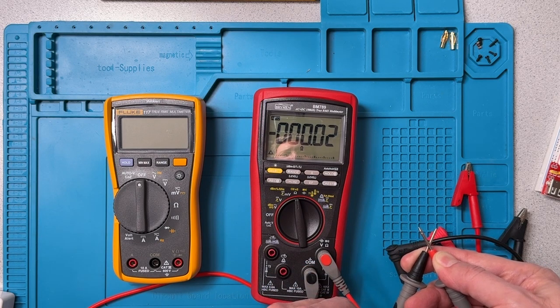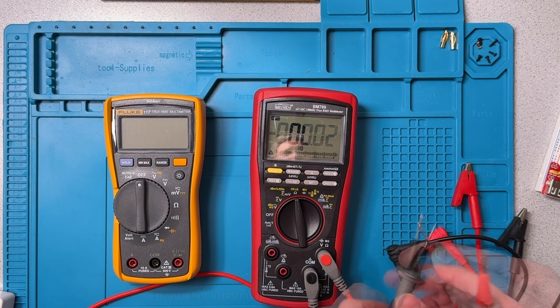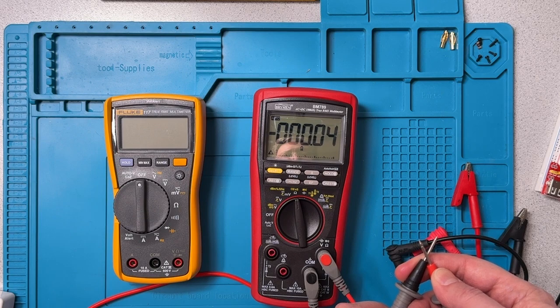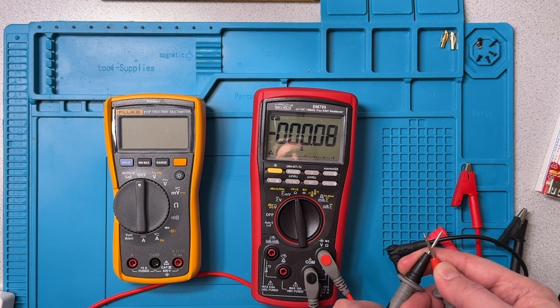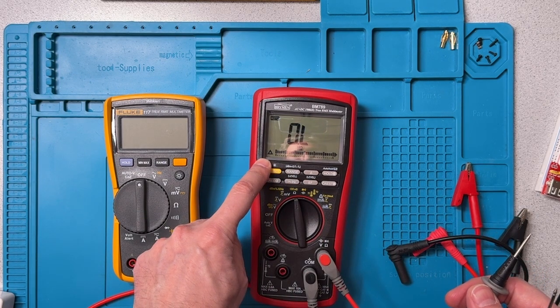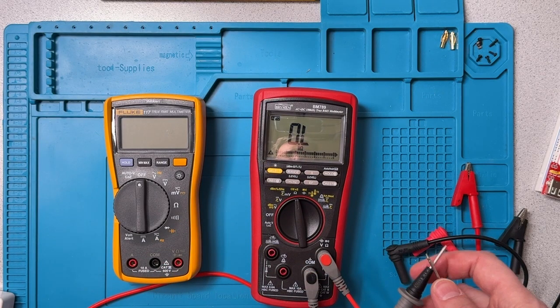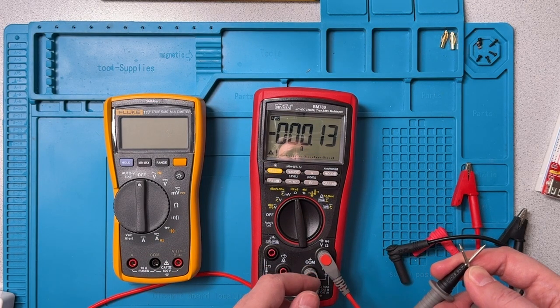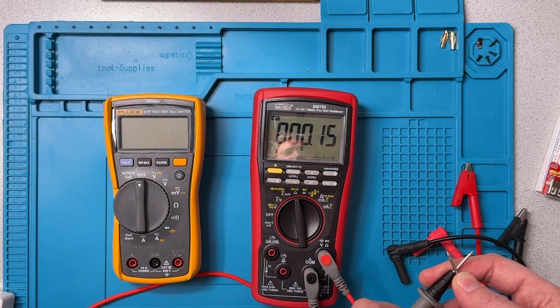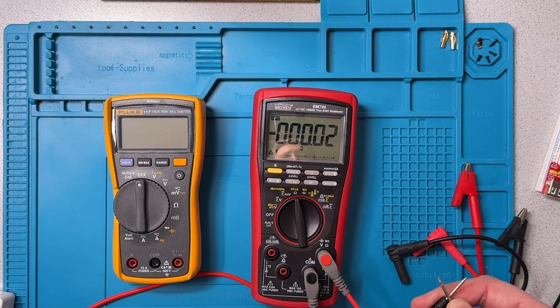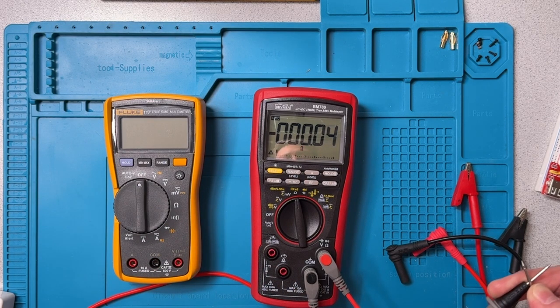And now it measures the difference between what we had been measuring and that delta point, and there's a little delta that appears in the bottom left corner to show that we're in the delta mode. And we can of course press delta again. We're out of that mode. Press it again, and you can see that it is a way of compensating for a reading. We want to compensate for a resistance or compensate for a voltage, and we want to see what the changed value is from some sort of a base.